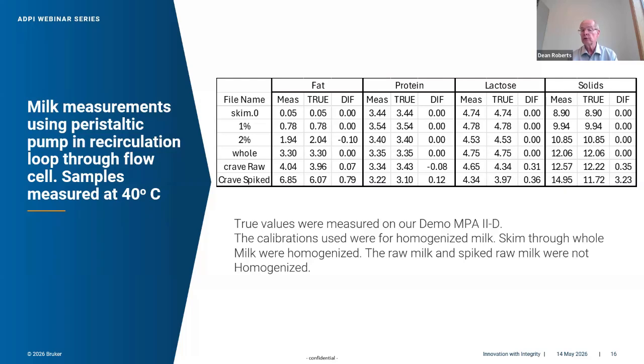So looking at the differences, I was at first in a little bit of disbelief. I didn't think that this was real. There's got to be some kind of an accident there. So I did it again, and I got the same thing. Now, these samples were all measured at 40 degrees C. I stuck a gallon bucket in a water bath at 40 C. I let it temperature stabilize, measured the sample, and did that for each one of these different samples, a skim, 1%, 2%. And there is actually no difference between the measured and true on these things.